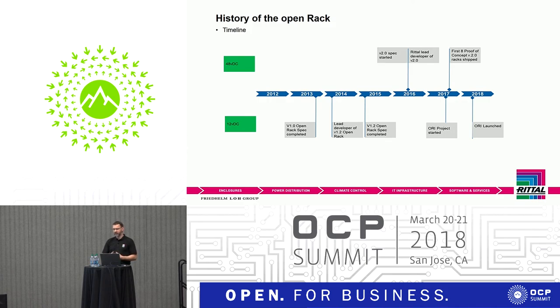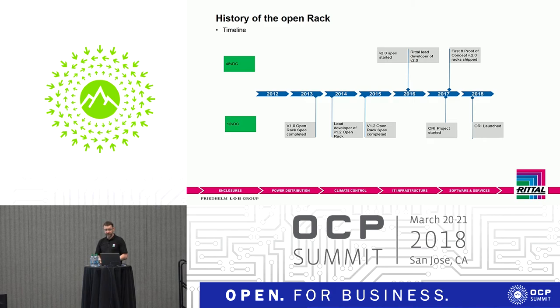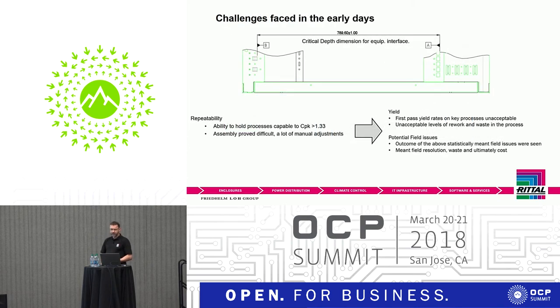In mid-2016 we moved to the v2 spec, which introduced 48-volt DC into the open compute specification. We were one of the lead developers on that v2 48-volt DC rack. We submitted eight proof-of-concept designs for DV testing in mid-2017, with six passing successful DV testing and ready for deployment. Mid-2017 also saw the start of the ORI project — Open Rack Improvement — and by 2018 the first ORI cabinets are being manufactured this week from our factory in Plymouth, UK.